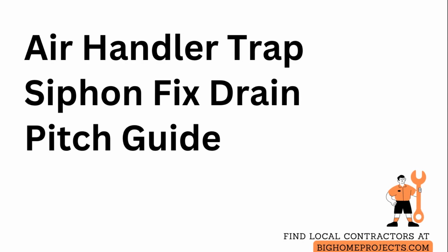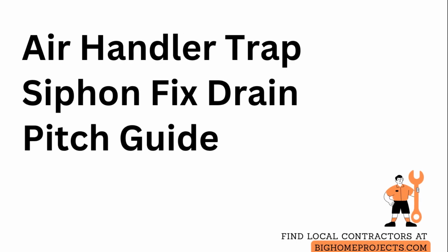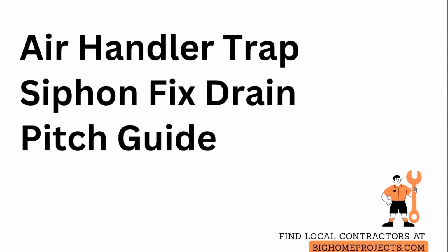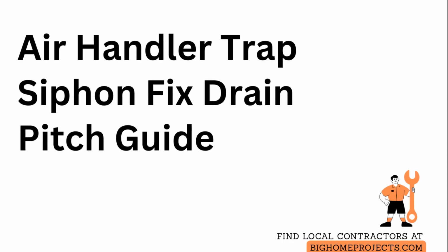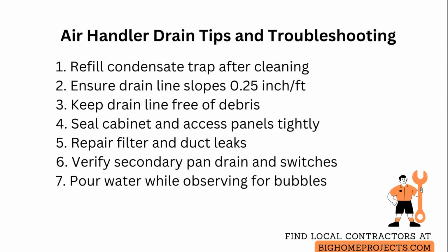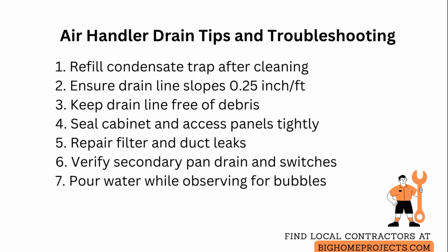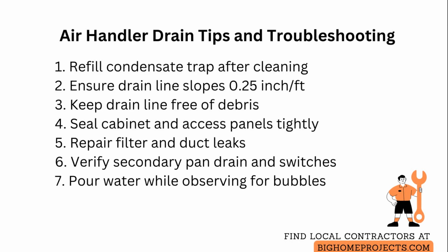Negative pressure inside an air handler can indeed interfere with drain line operation and lead to failed drainage. When an air handler develops negative pressure relative to the drain pan or the condensate trap, air can be drawn through the trap and disrupt the normal gravity flow of condensate.